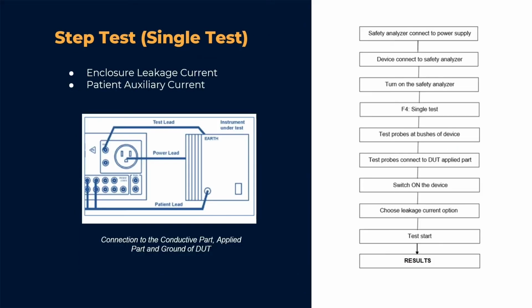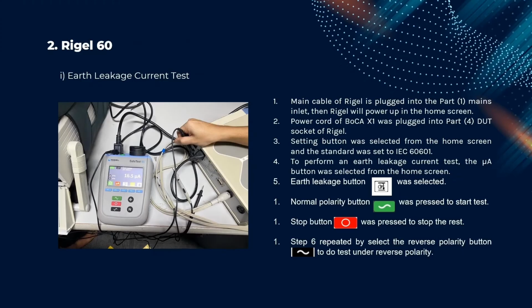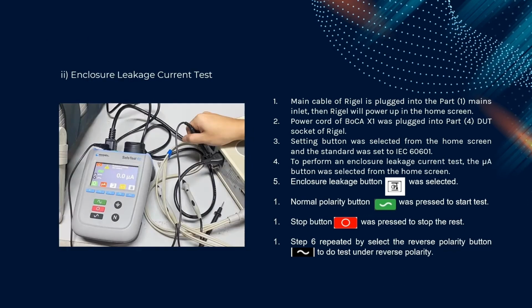Next, for the single test, we are doing 2 tests, which are the enclosure leakage current and patient auxiliary current test. We connect the Bender to the power supply and the device, then choose the option F4, which is single test. Next, we move to the Rigel 60. We are doing the testing for earth leakage current and enclosure leakage current since the bioimpedance BOCA is a class 1 type BF device. So here is the test procedure for both tests.